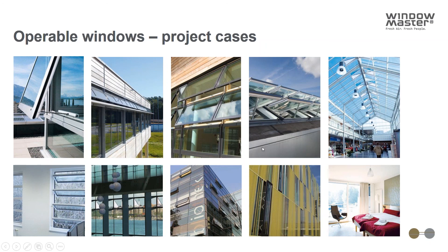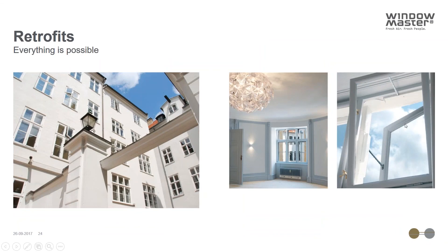Moving to control systems: what we learned from Ed's case studies links to both the control system and the hardware — the window operator. Window actuators can be noisy and visible, operators are either fully open or fully closed leading to poor control, and there is a lack of an integrated system designed to make natural ventilation perform properly. These are the issues I will address in the next slides.